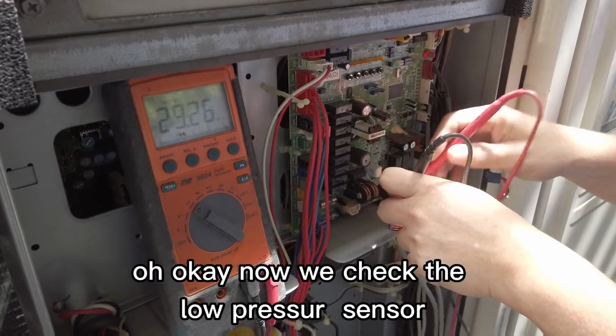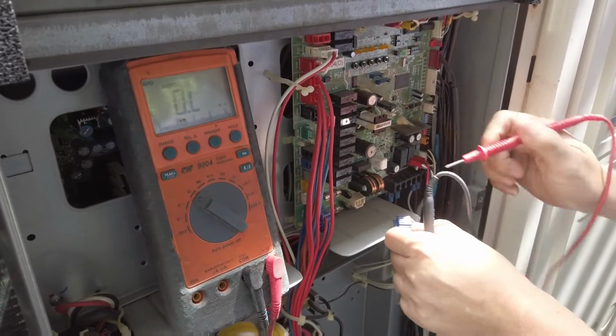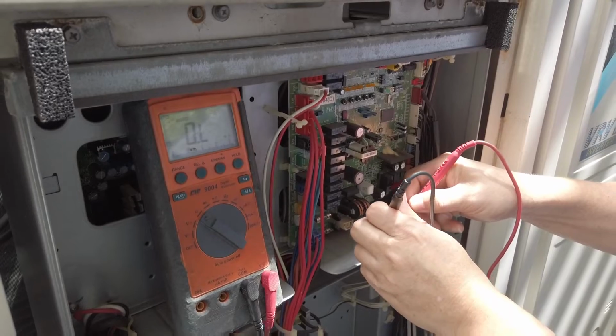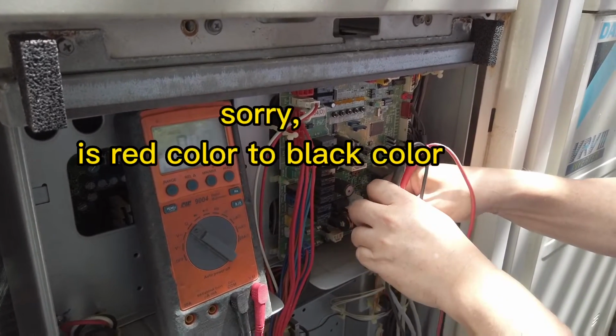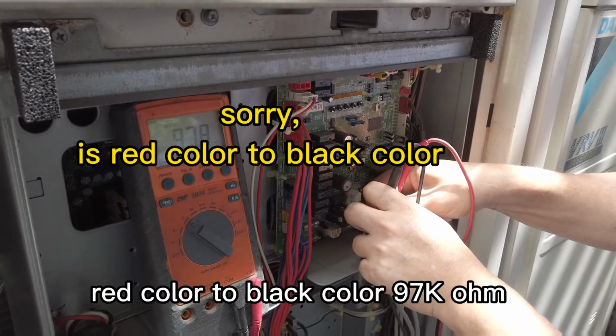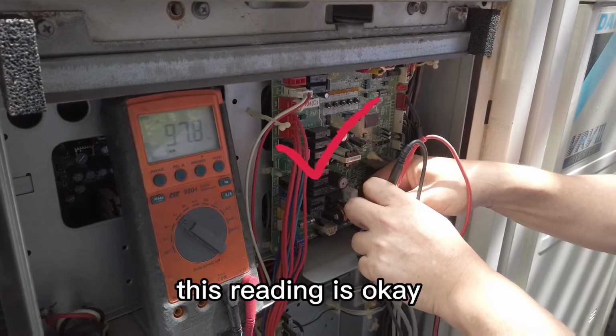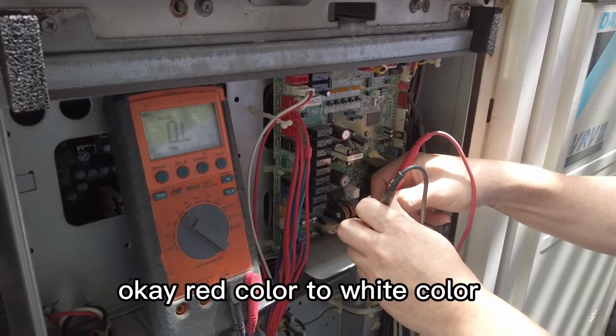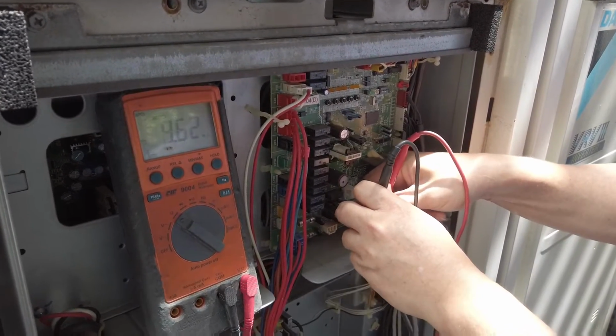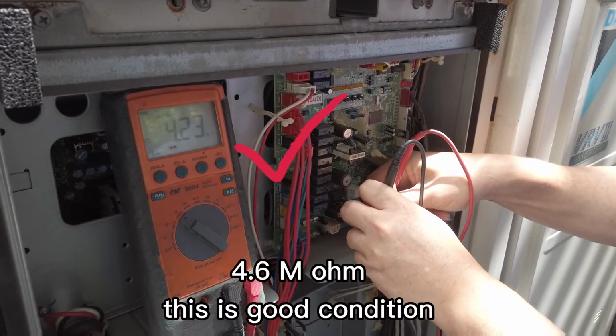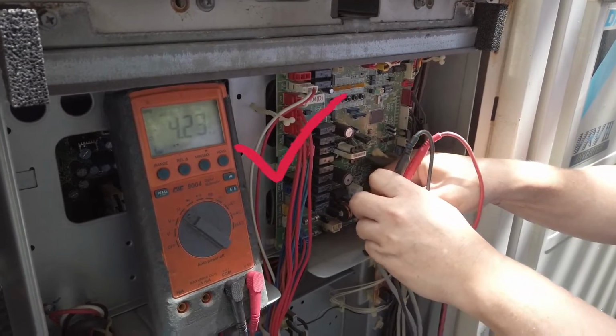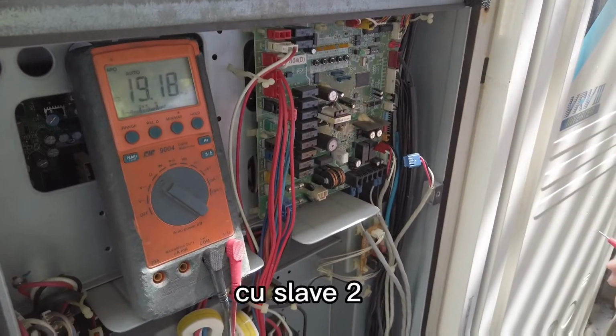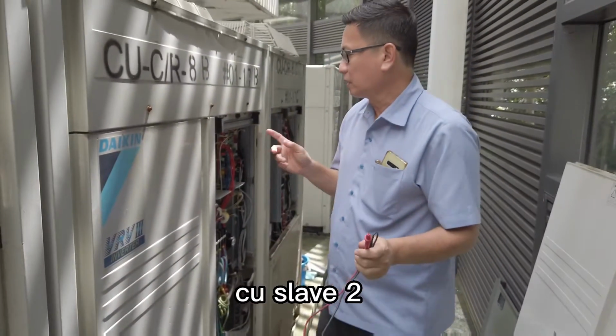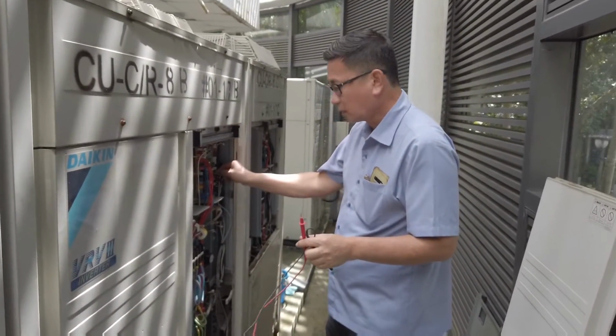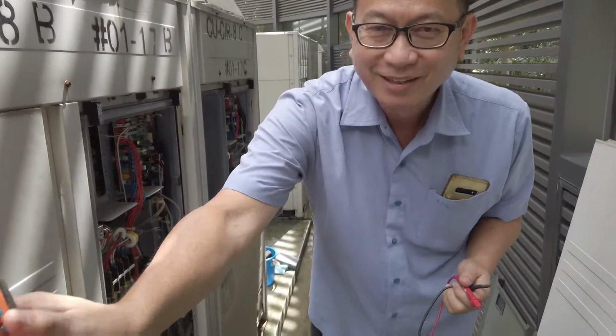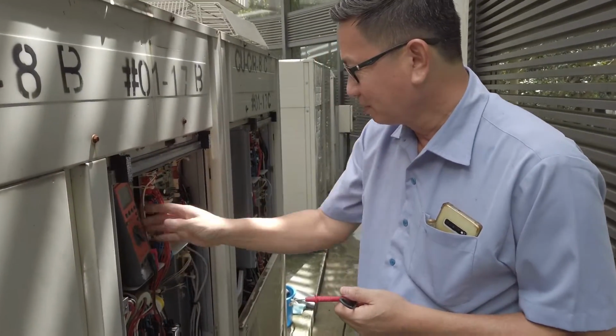Okay, now we check the low pressure sensor. Red color to black color, 97 kilo ohm. This reading is okay. Okay, red color to white color, 4.6 mega ohm. This is good condition. Okay, now we check the slave unit.